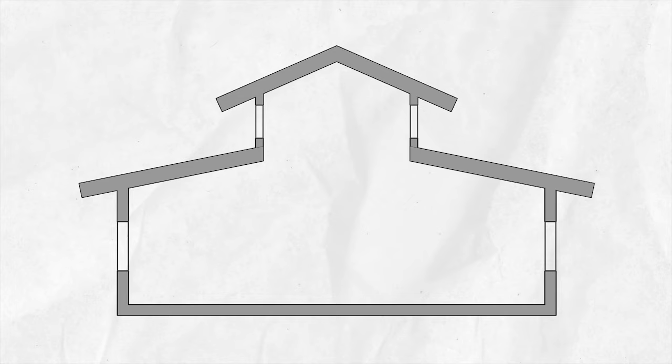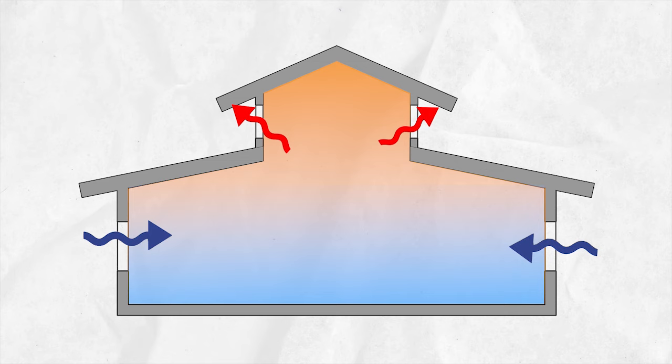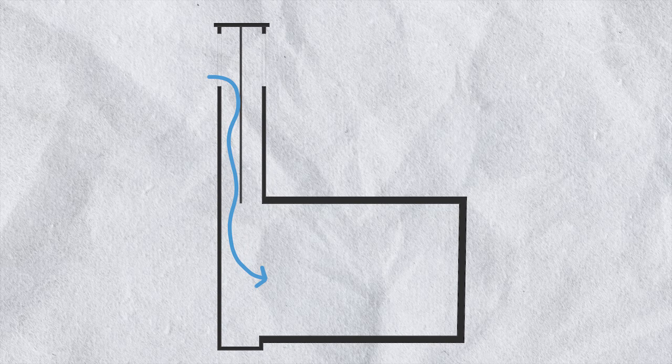Stack effect is a secondary mechanism that aids the performance of the wind effect. It is based on the density difference between fresh and indoor air due to temperature differences. Generally, cool, denser air settles down, and warm, less dense air moves up. As fresh air enters through the windward opening, the stack effect aids its downward movement and helps raise hot indoor air to the leeward side.